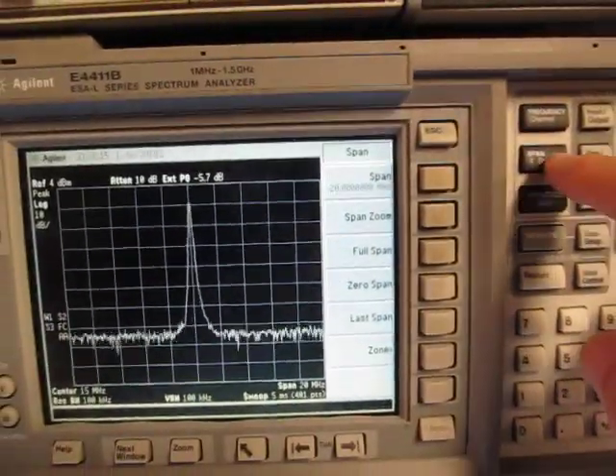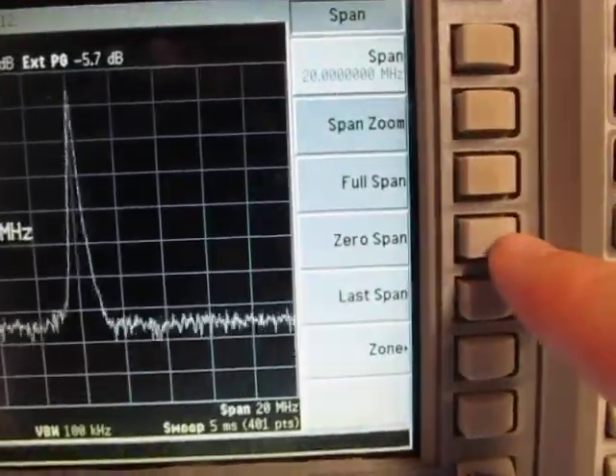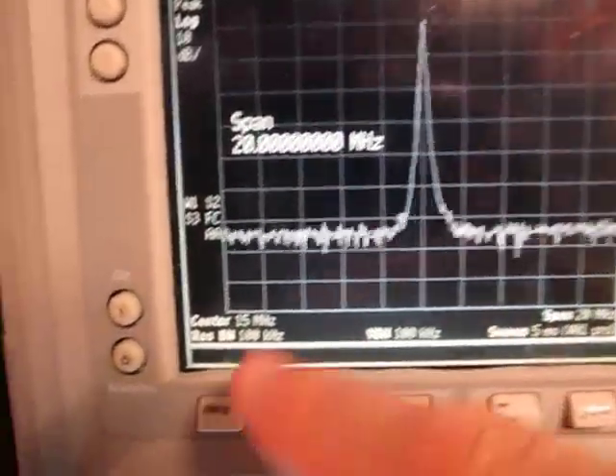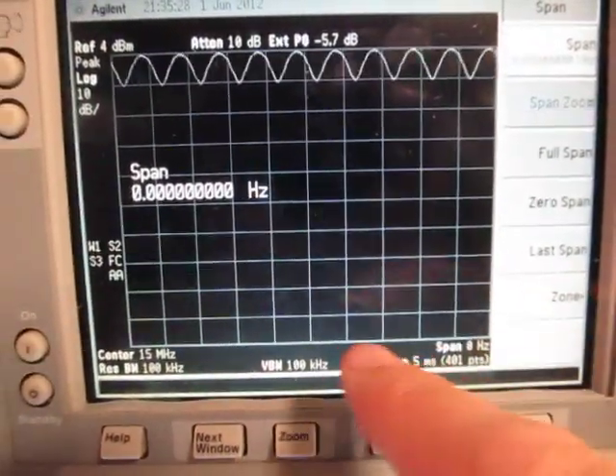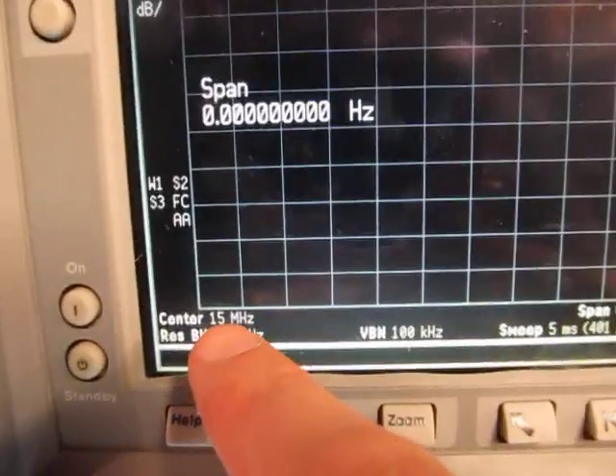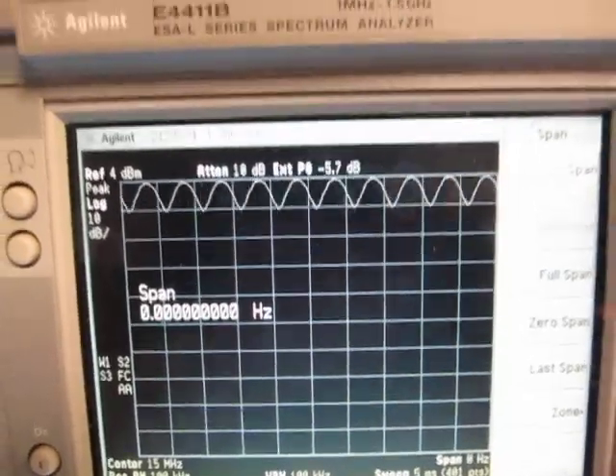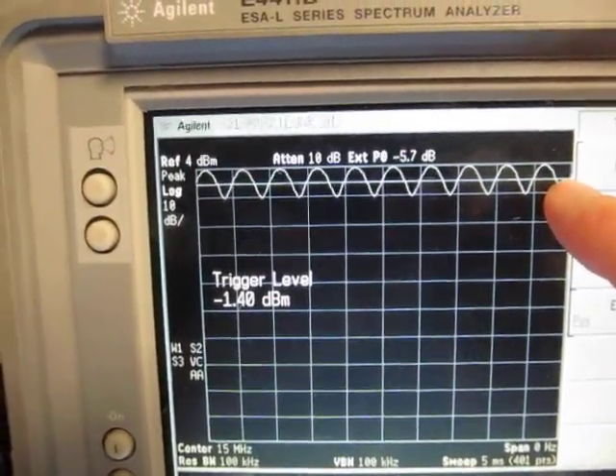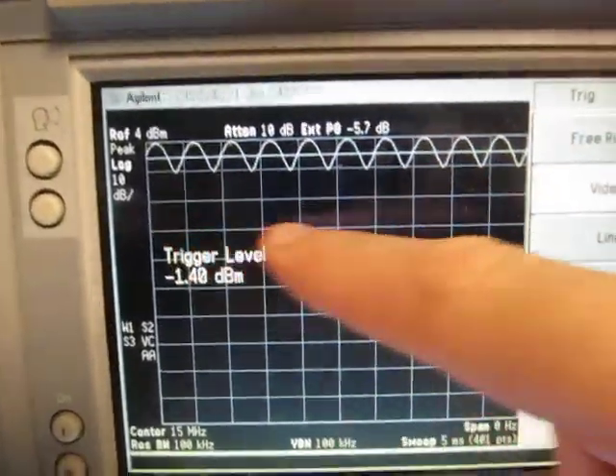Now, if I just hit my span key and I change from 20 megahertz span down to zero span, now I'm going to take that resolution bandwidth filter, which right now is set to 100 kilohertz wide. I'm going to just park that at the center frequency of 15 megahertz. And there's my resulting display. I'll do a quick little video trigger here so I can trigger on that signal and make it sit still. So now I can actually see the amplitude variation over time.